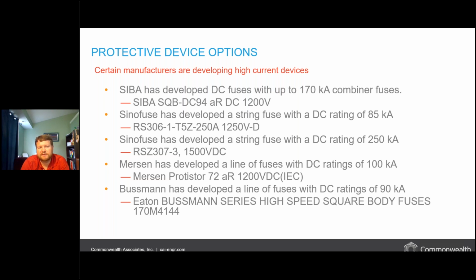We're also seeing that Sinofuse also has string fuses. These are the fuses that go on top of the battery stacks themselves, with very high ratings as well, up to 250,000 amps, and these are tested ratings by the manufacturers. Mersen has a 100,000 amp string fuse rating in their Protistor series, and Bussmann has a line of DC fuses up to 90,000 amps. So there is some equipment that can deal with these high fault currents, but as you can see, with some of the fault currents we saw from our example, even devices with very high fault current ratings are very near what we're experiencing in the field.